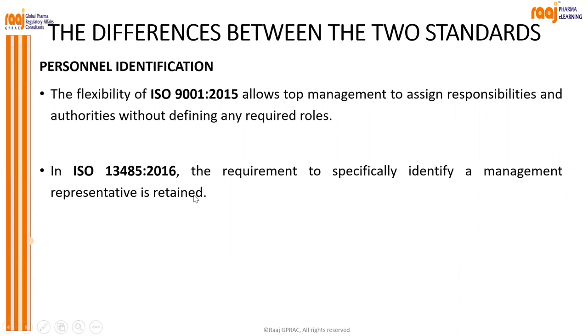Whereas for ISO 13485, defining and taking responsibilities of the MR is very important. So we have to specifically identify the suitable person who is competent enough to carry out all those responsibilities, so that the MR is retained. So this is a mandatory requirement of the MR in 13485.